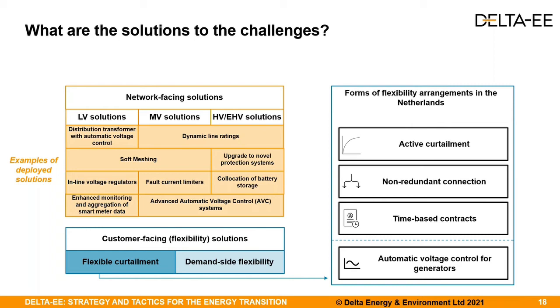Then we have non-redundant connections. We basically use the transport capacity of all the transformers available at the substation for solar and wind farms. For example, if there are 3 transformers available, we use all of them to transport solar and wind energy. If we have problems with one of the transformers, or have to do maintenance on one, we will curtail the production of the production units until the maintenance or non-availability of the transformer is done.